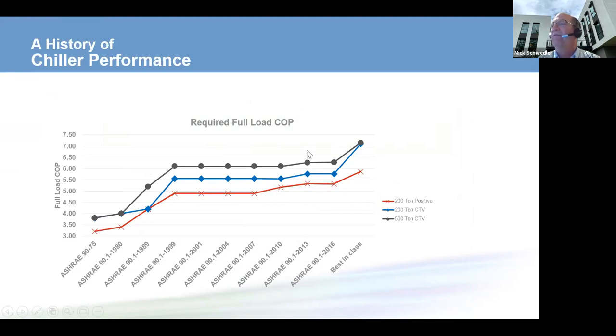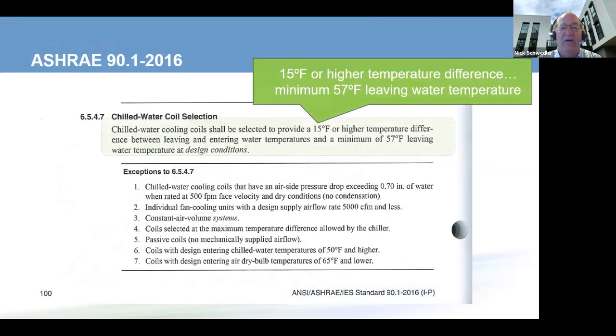COP has gone up by 50 to 70% over the last 40 years. Pump performance hasn't changed. At part load, we now use variable speed drives. Same thing on cooling tower fans. But the chiller performance really has led us to, well, you have to have the chiller work harder. Its COP is between 6 and 7. If a pump has an efficiency of 70%, its COP is 0.7. Work the most efficient part of the chiller system a little bit harder.